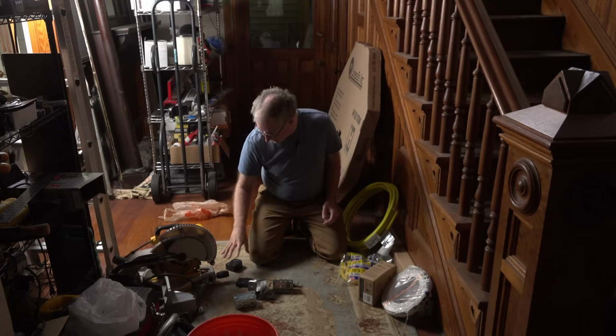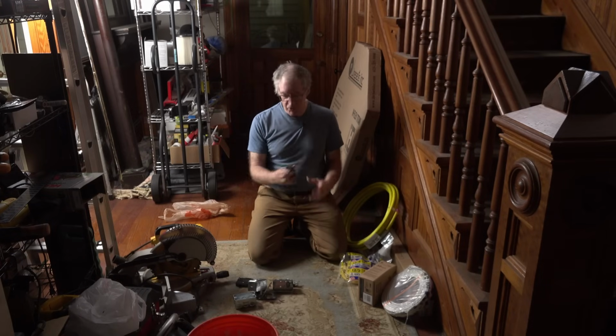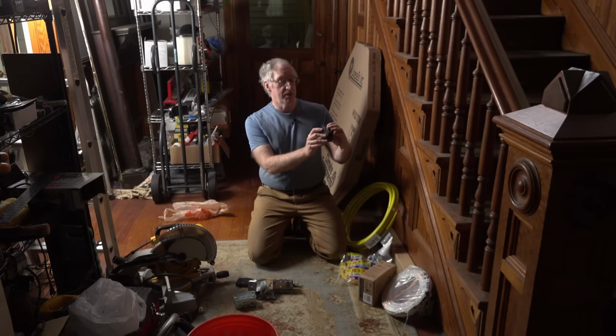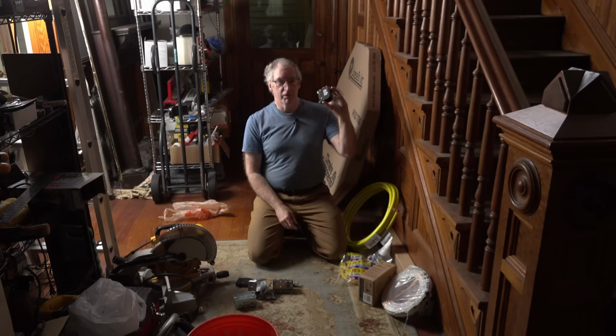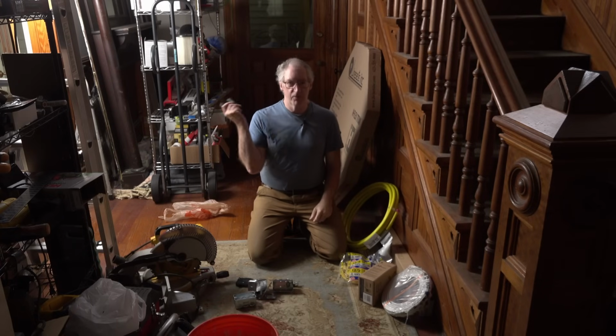And let's see, we need a circuit breaker. This one here is the larger of the two, so this is probably it. It's a 20 amp 2-pole breaker, which is sized correctly for that outdoor unit.